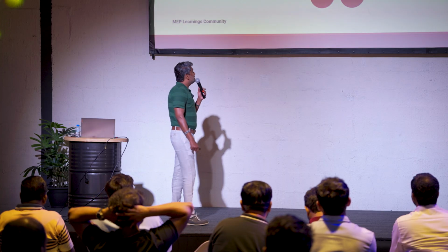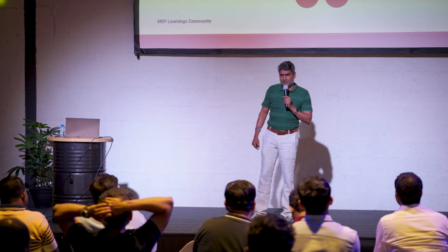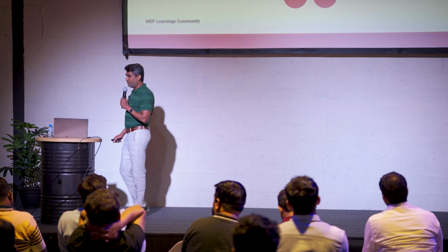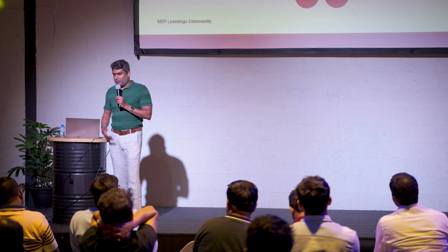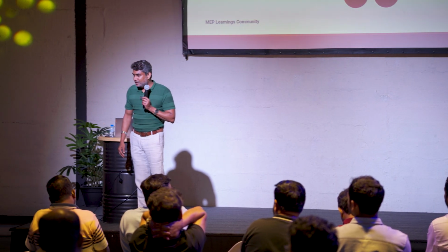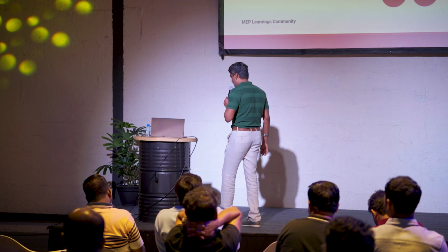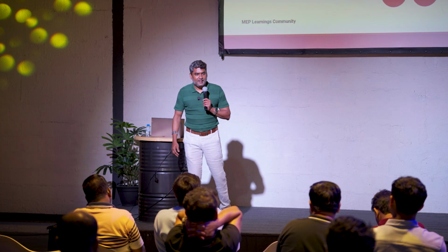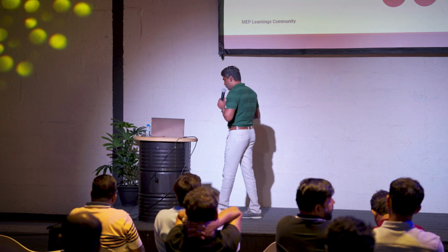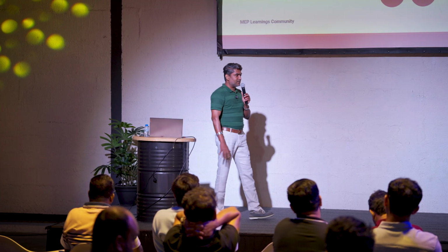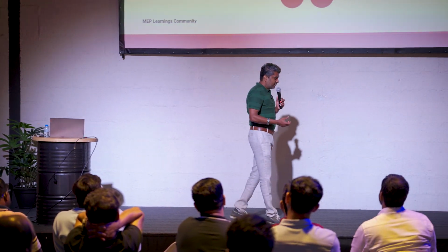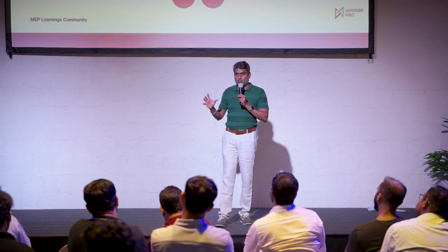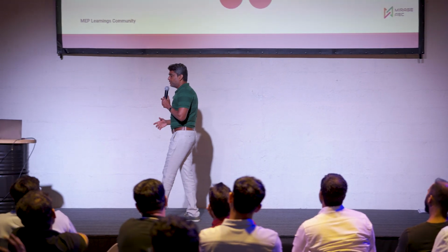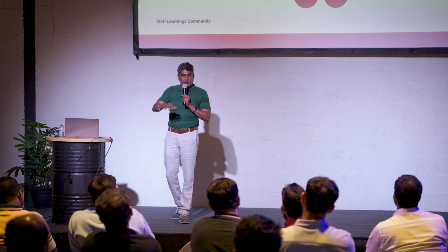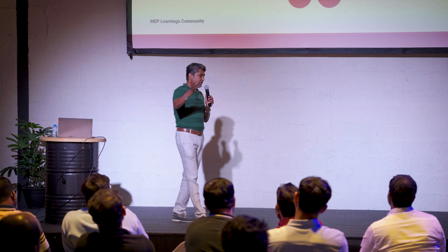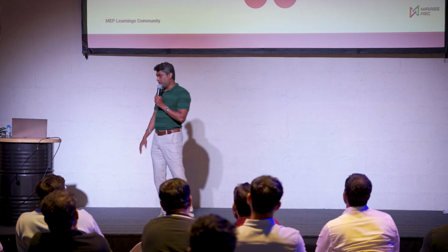The next item is MSDs and MSFDs. What do you think is their purpose, and why should they be integrated? Why do we have to shut down the fire dampers? In a building, you will notice fire compartments—certain areas which are sensitive, have more potential for fire, or are critical areas with important equipment or data that the client wants to protect. Those areas are separated by a two-hour fire compartment so the fire should not spread from the protected area to outside, and vice versa.